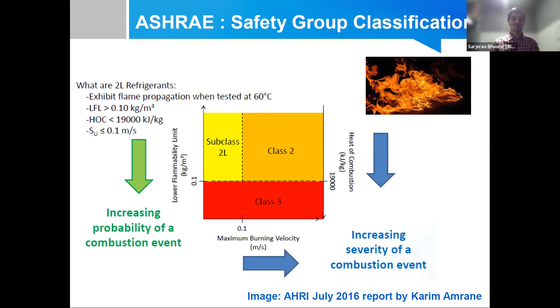Class 2 and class 3 are basically distinguished based on two factors, that is lower flammability limit and heat of combustion. For example, a lower flammability limit of 0.1 kg of refrigerant in 1 meter cube. If an ignition source is present and that refrigerant's lower flammability limit is 0.09, let's say, then it is categorized as a class 3 refrigerant, since there is an increasing probability of a combustion event. Plus, it should have more than 19,000 kilojoules per kg of heat of combustion. So that is the thing. That is how these are distinguished as per ASHRAE, and a lot of research went into distinguishing these categories, that is, subclass 2L.